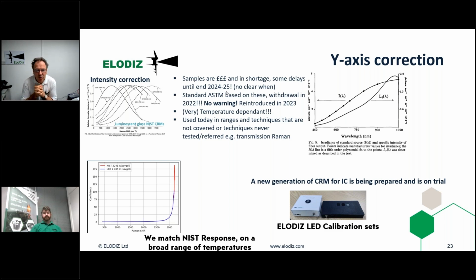So Elodiz has been developing for the last couple of years a new strategy to try to do y-axis correction for intensity in Raman spectroscopy, and we have developed a series of LEDs that can be used to correct the intensity. The example that we have here on the left-hand side is a comparison of the correlation factor between the NIST standard and the Elodiz standard. So it's a perfect match. The difference that we're introducing here is that the range can be broader, and we have no problem in terms of temperature dependence. It's much more stable.